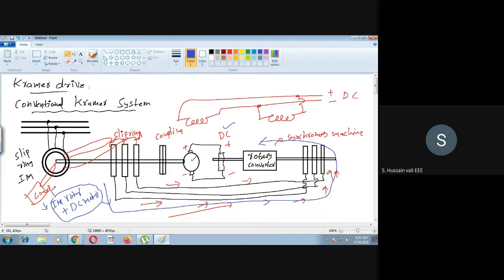In case of the Scherbius drive, what did you find out? The power which you collect from the slip rings goes directly through the bus bars. Recall, 3 bus bars were there. So it goes directly to the bus bar. The slip power which you connect here, you convert that into DC, then you convert once again into AC, then you have a transformer, then through the transformer it goes to the bus bar. That is what you have seen in case of the Scherbius drive.